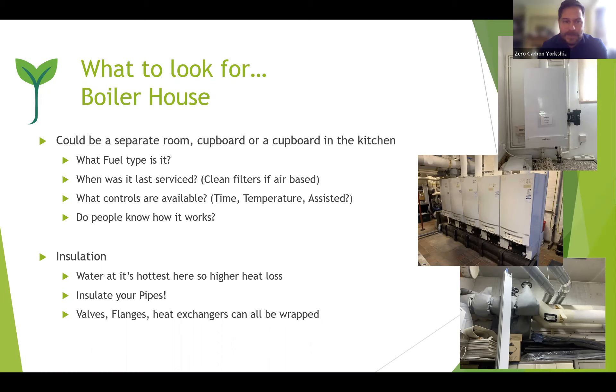A quick word on insulation particularly in the boiler house or around your boiler — water is at its hottest here so the temperature gradient is highest and heat loss potential is greatest. Insulate your pipes. Go to B&Q, get some insulation, and just insulate them. For bigger systems you can also insulate valves, flanges, and heat exchangers — custom wraps are common now with payback usually within three months. A good test: if you walk into your boiler house and you're warm in there, that energy should be pushing into the building, not into the plant room.